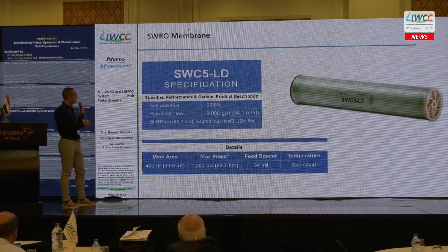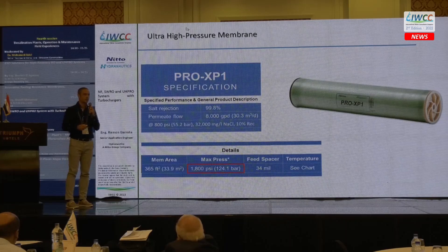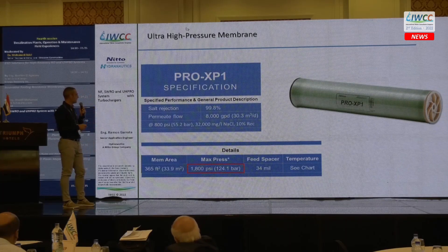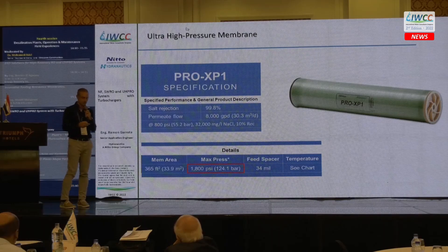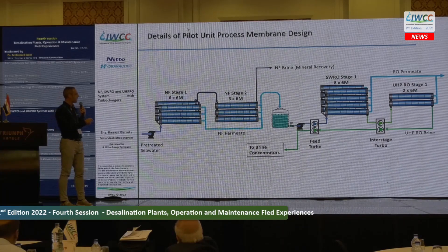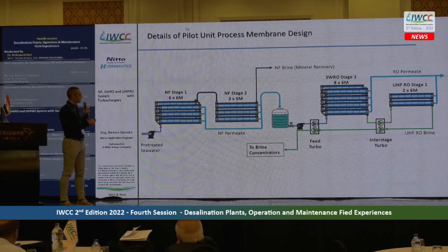The seawater RO membrane used is the SWC5 LD, well known in the market — a compromise between high rejection and high flow, with 99.8% rejection, a flow of 9,000 GPD, operating at standard seawater pressure of 800 psi. For the high-pressure membrane, we used the PRO-XP1, also 99.8% rejection with slightly lower permeate flow, able to operate up to 1,800 psi feed pressure to achieve higher concentration. The pilot unit NF system has two stages with six elements per vessel.